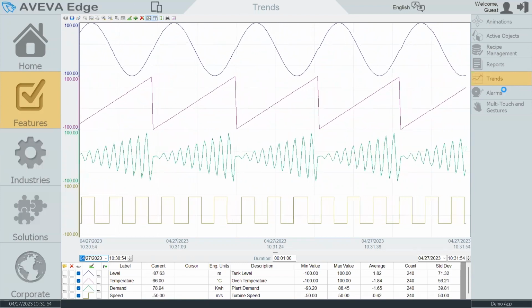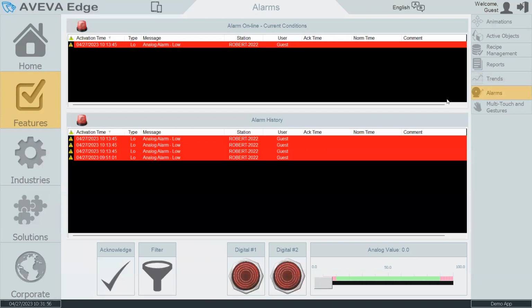The alarm window is also very good. So for instance, if your tank level is going to overflow, you can trigger an alarm. It'll pop up a screen similar to this, and you could acknowledge it, or fix the problem, and then the alarm will disappear. If the alarm doesn't disappear, then you need to send someone there really quickly to fix the problem.